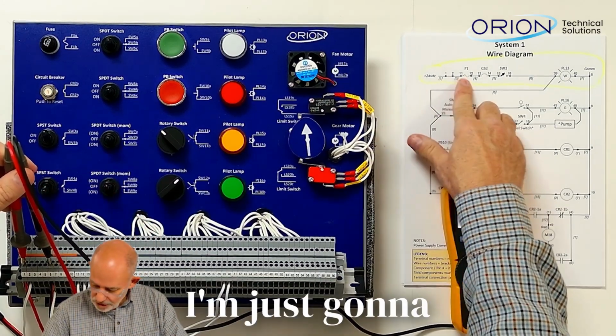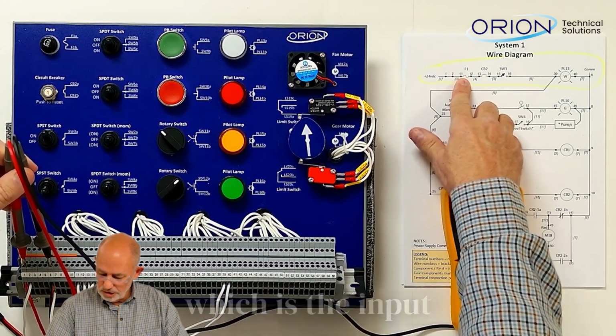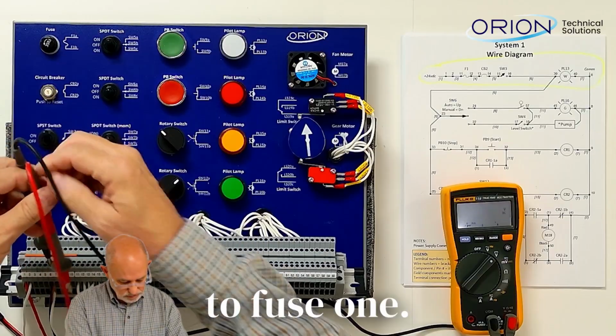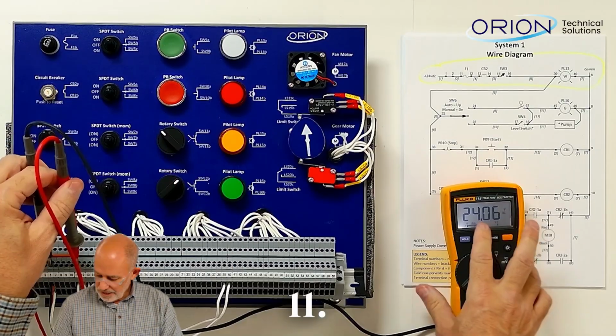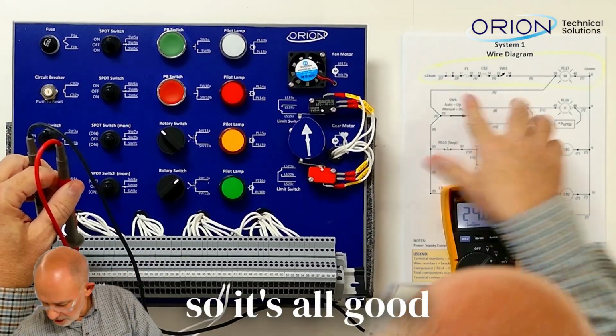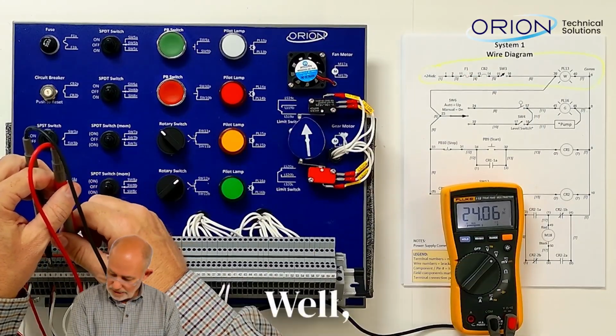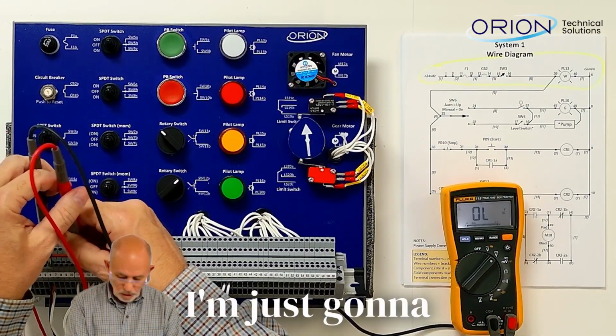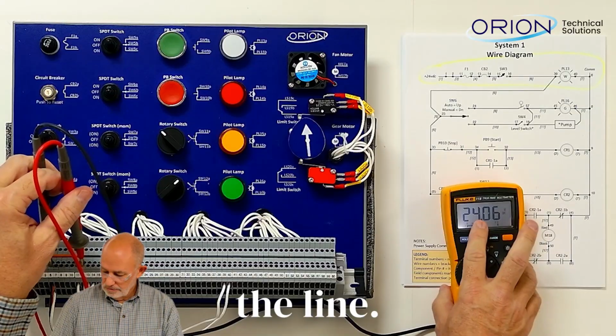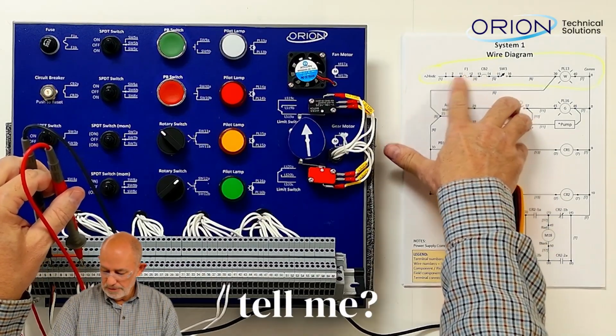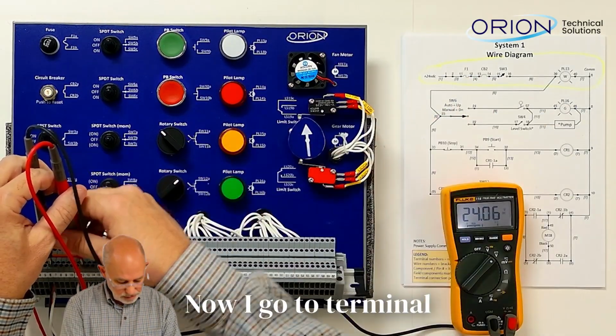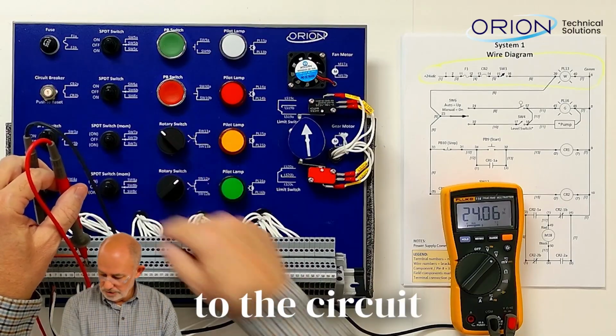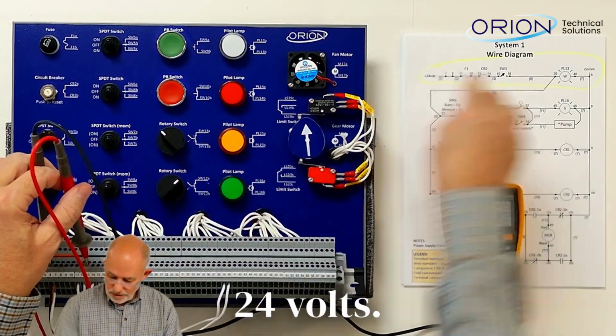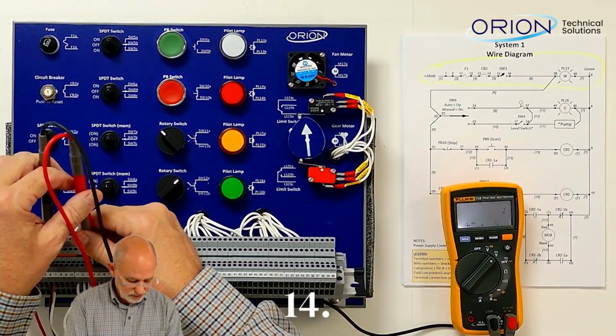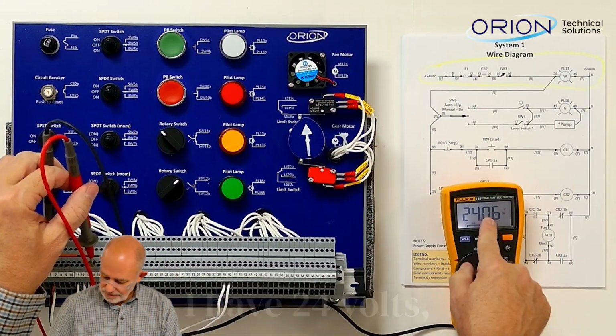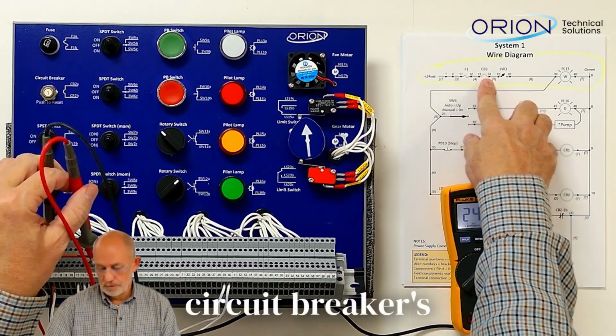So now I'm just going to jump over to terminal block 11, which is the input to fuse 1. Terminal block 11. Okay, I've got 24 volts there, so it's all good up to the fuse. Well, now let's check terminal block 12. I'm just going to walk right down the line. Well, that's 24 volts, so what's it tell me? It tells me it's good to here. Now I go to terminal block 13, which is the input to the circuit breaker, 24 volts. Next, I'm going to go to 14. Terminal block 14, I have 24 volts, which tells me the circuit breaker's good.